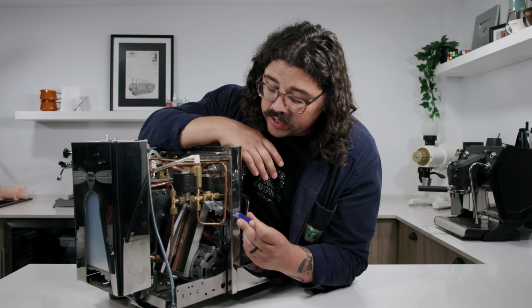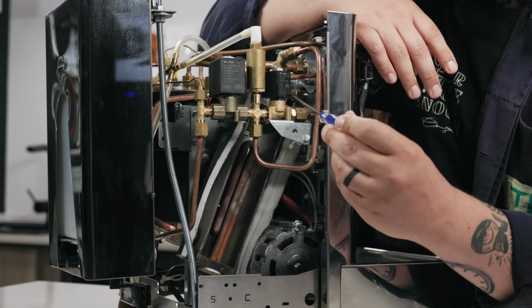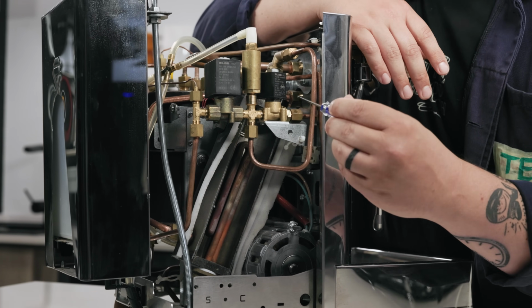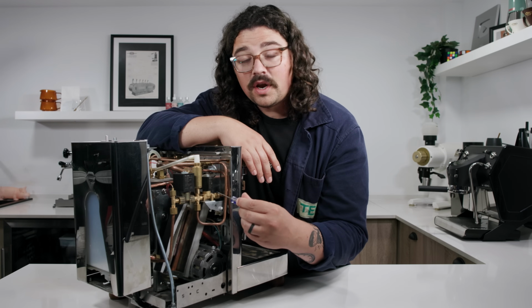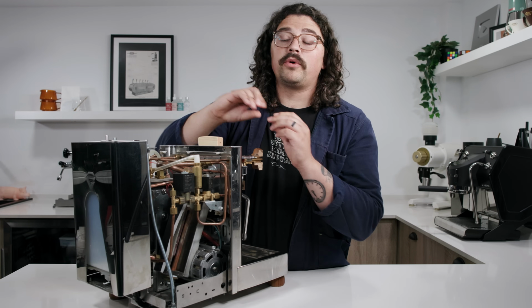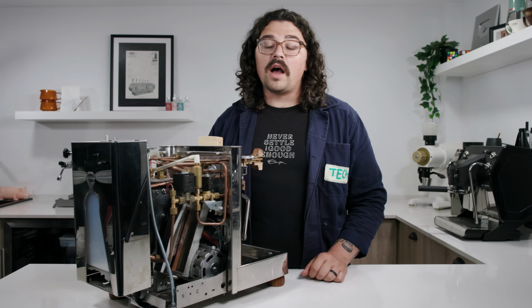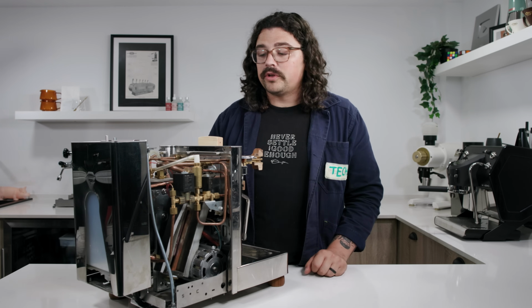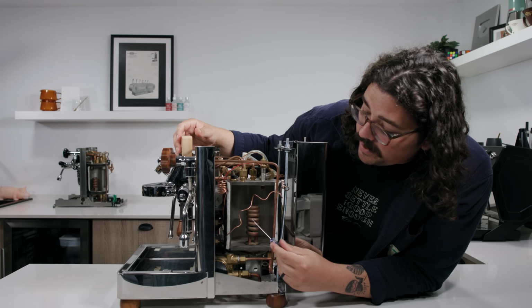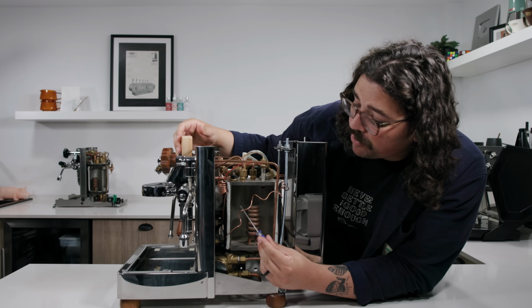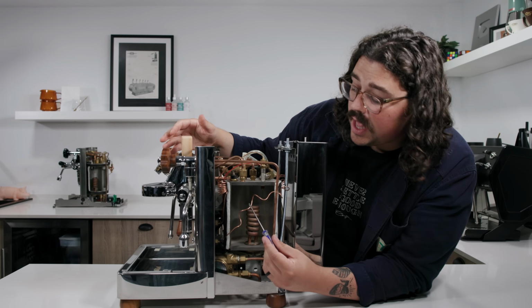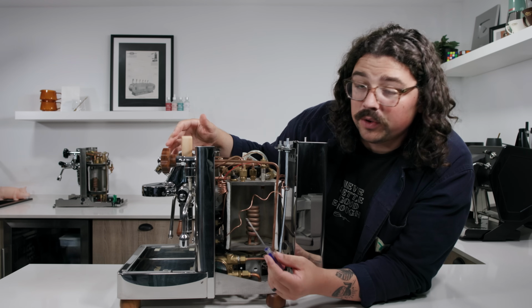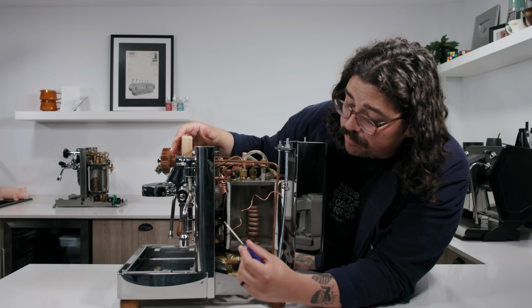As we keep moving along here, we have another solenoid, and then we have the inlet into the steam boiler. So just like on the Mara X, we have another inlet here that goes over to our steam boiler, which is the big boiler on the other side. Much larger boiler. So as you see here, big heating element inside of the steam boiler. We also take pressure of the steam boiler, this is the pressure reader, and it'll show on the pressure gauge on the front. It connects to the pressure gauge there.